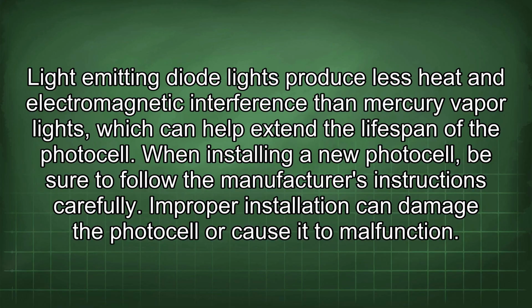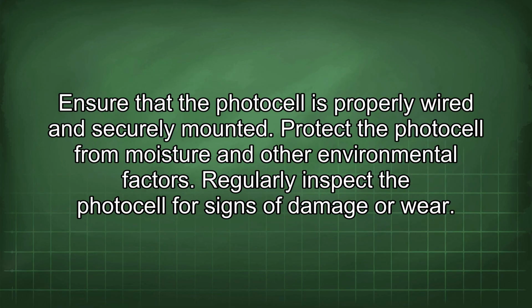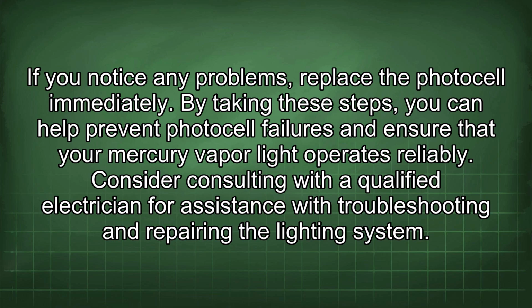When installing a new photocell, be sure to follow the manufacturer's instructions carefully. Improper installation can damage the photocell or cause it to malfunction. Ensure that the photocell is properly wired and securely mounted. Protect the photocell from moisture and other environmental factors. Regularly inspect the photocell for signs of damage or wear. If you notice any problems, replace the photocell immediately. By taking these steps, you can help prevent photocell failures and ensure that your mercury vapor light operates reliably. Consider consulting with a qualified electrician for assistance with troubleshooting and repairing the lighting system.